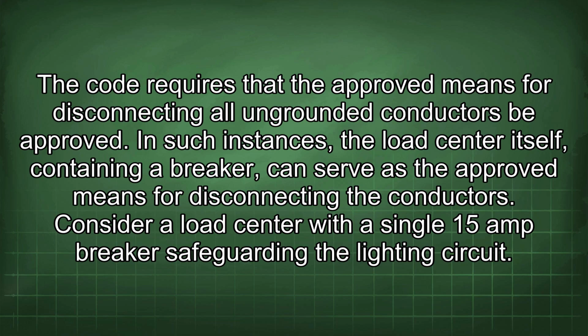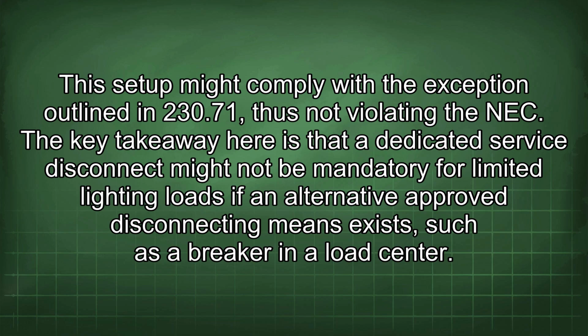Consider a load center with a single 15-amp breaker safeguarding the lighting circuit. This setup might comply with the exception outlined in 230.71, thus not violating the NEC. The key takeaway here is that a dedicated service disconnect might not be mandatory for limited lighting loads if an alternative approved disconnecting means exists, such as a breaker in a load center.